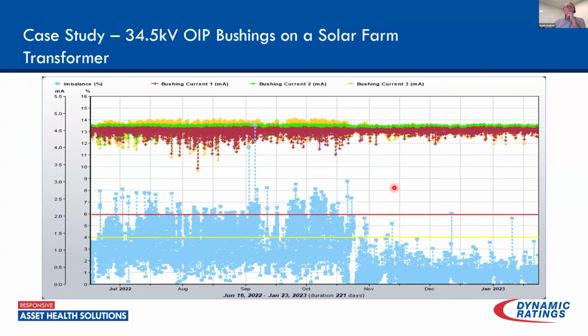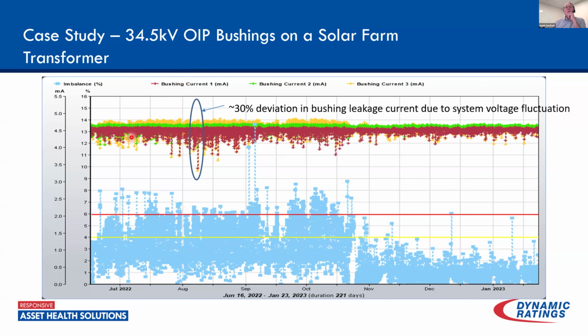As we looked at the data more, I started looking at the individual leakage currents and leakage current angles, and what I saw again was large deviations due to system voltage fluctuations. In this case, I've got a 30% deviation in bushing leakage current. What I can see is that it's affecting two phases. My center phase, bushing current 2, is much less. All of that could be driving imbalance currents and problems within the system, and how quickly these deviations occur could be putting stress on the equipment.